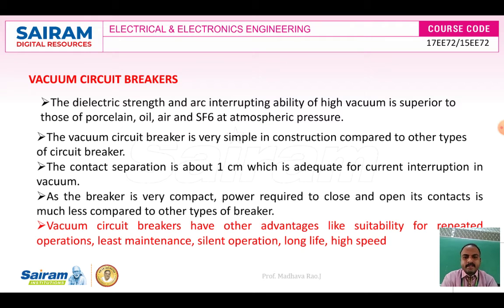And the vacuum circuit breaker has a very simple construction. Construction wise it is very simple and compact compared to other types of circuit breakers. So the size is very small and the construction is very simple. The contact separation is about 1 centimeter, which is adequate for current interruption in vacuum. The contact separation is only 1 centimeter. It's not like meters, so very little contact separation.